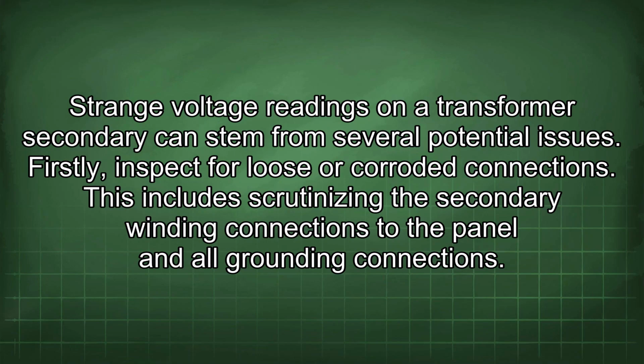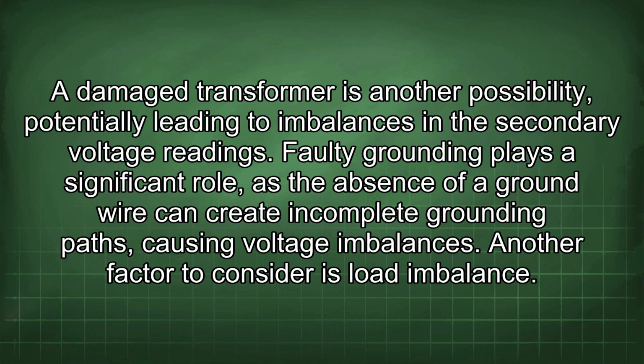Strange voltage readings on a transformer secondary can stem from several potential issues. Firstly, inspect for loose or corroded connections. This includes scrutinizing the secondary winding connections to the panel and all grounding connections. A damaged transformer is another possibility, potentially leading to imbalances in the secondary voltage readings.